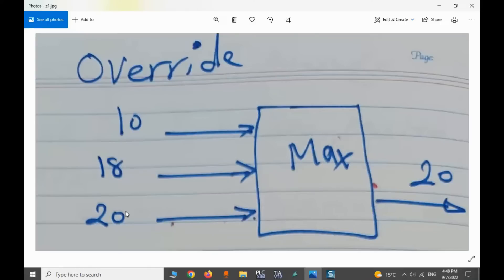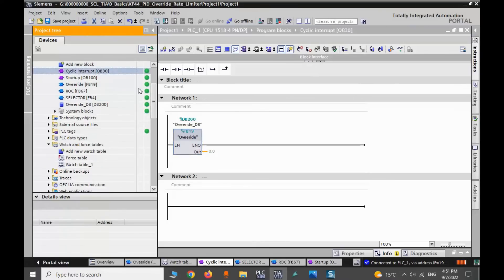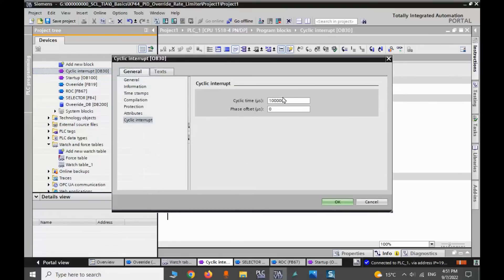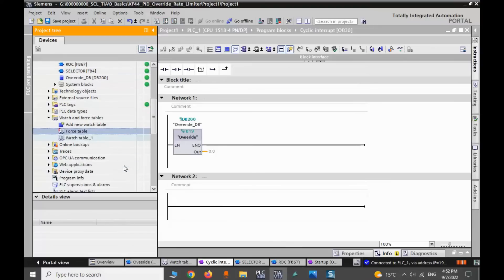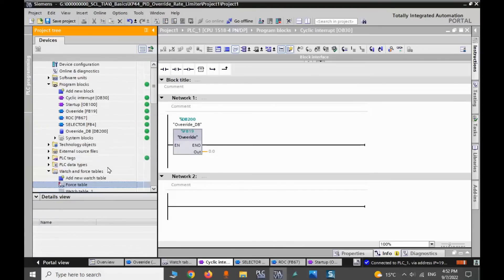The output will be 20. In a real machine, these values are dynamic — some can be constant and some will be dynamic values, and the output may change. Possibly we are at 20, and after a while we may jump to 70 based on process conditions. So we need to have a velocity limit block in OB30, and we need to make sure that the cyclic interrupt is 100 ms — yes, it's 100 ms or 0.1 second.